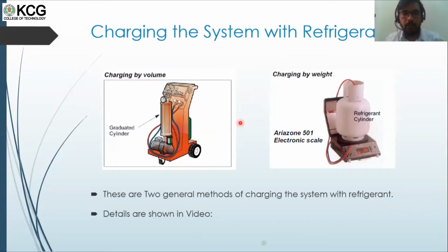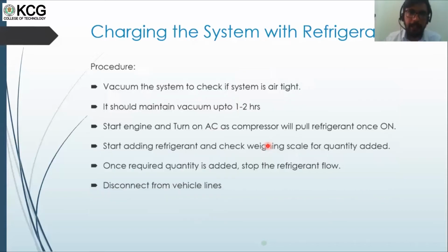So basically two methods are used in charging the system: charging by volume and charging by weight. Personally, I feel charging by weight is more accurate as compared to volume, as volume may change according to your ambient temperature. So density may vary and you may end up with inaccurate reading. So I would prefer this method, and these are the steps for charging the system with refrigerant.